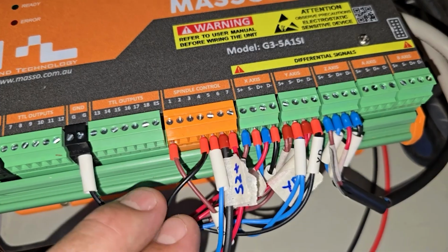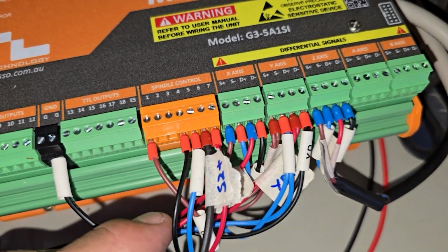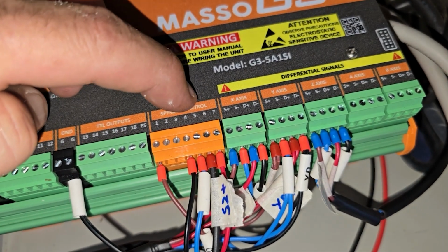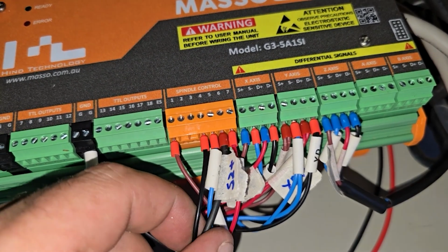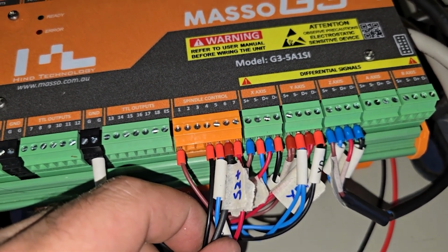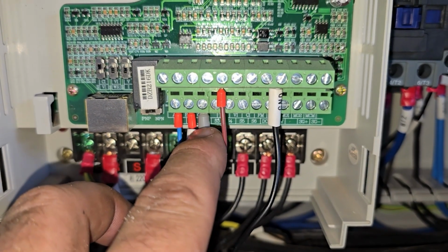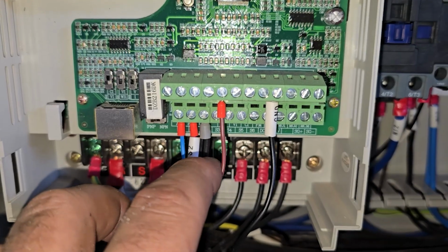This is the ground, and then I had to add a second wire over here because the forward and reverse positive terminals, 6 and 4 I think, have to be connected to the same DCM terminal on the VFD. As you can see over here, this terminal is the DCM, and those two are connected.